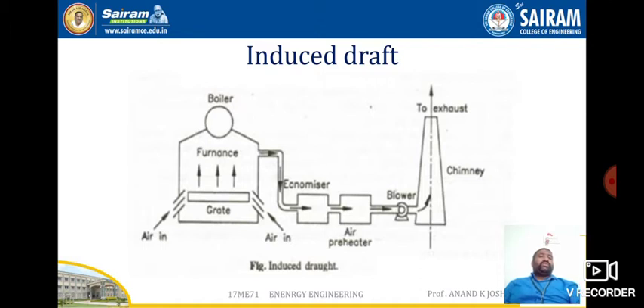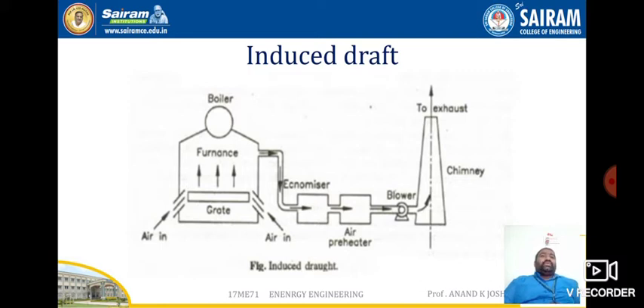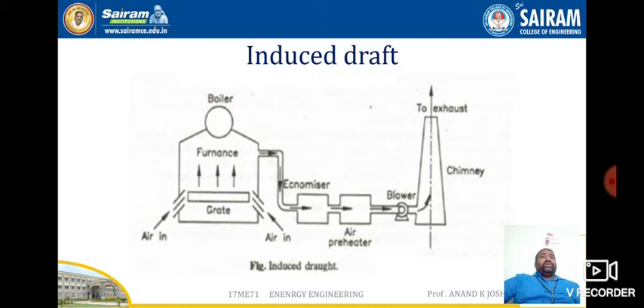The next type is the induced draft system. Here the blower is located near the base of the chimney, unlike the forced draft where it is near the furnace. Air is sucked through the system, reducing pressure below atmospheric. The induced draft fan sucks the burnt gases from the furnace, reducing pressure inside the furnace below atmospheric and inducing atmospheric air to flow through the furnace. The draft produced is independent of the temperature of the hot gases, so gases may be discharged as cold as possible after extracting as much heat as possible through the preheater.